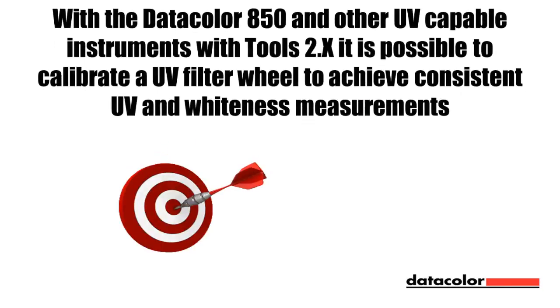Spectrophotometers like the 850 with a UV filter wheel can adjust the amount of UV in its light source to a standardized UV amount. In this way, spectrophotometers can control the amount of UV so that they can read like one another. Standards for UV are produced to help calibrate spectrophotometers' UV amounts. The standard that we will look at today is the CIE Whiteness Standard provided by AATCC. The instrument we use to calibrate the UV will be the Datacolor 850.